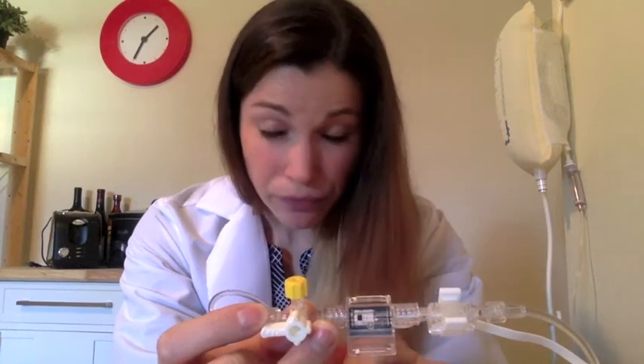So in order to allow this to happen, we need this nice stopcock to turn off to the patient. And since this side is going to the patient, we're going to go ahead and turn it off. And then we need it to be open to air. So we're going to theoretically take that yellow cap off. So now your transducer, you have a nice clear line going through it into atmosphere. You're going to go ahead on your monitor and push a nice convenient 0 button, and you should get a 0 up on the monitor. If you do not do this, you're going to get a bunch of question marks. So it's very good to 0 before you insert, immediately after insertion, and at least every 8 hours to ensure that your measurement is accurate.